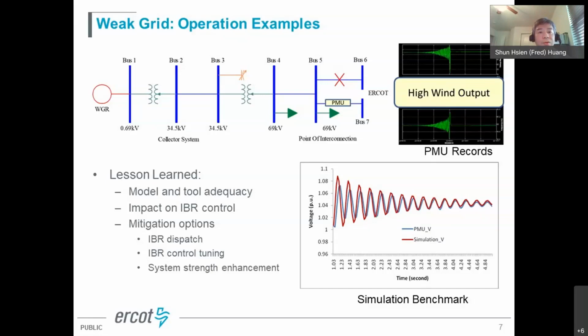The second option is obviously tuning - if you're aware of the condition, you may be able to properly tune the project for reliable response. But there's a caveat, as Sebastian mentioned: if the system continues to evolve, we need a process to regularly review the controller in the area and retune as necessary over time. Finally, there are multiple ways to improve system strength from a planning perspective, such as synchronous condensers, new circuits, or other ways to reduce impedance.